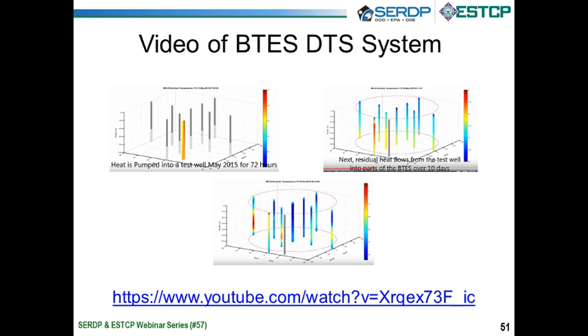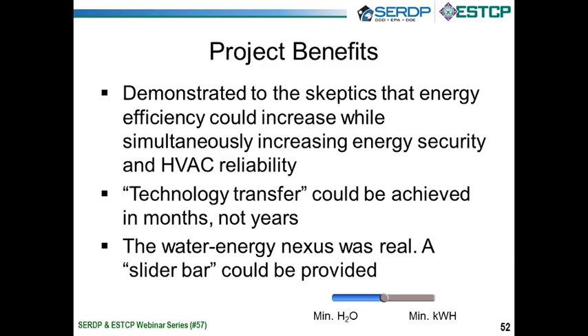The 3 slides there illustrate the heat we pumped down in the upper left corner during the thermal conductivity test. The second slide represents that heat flowing out into the bore field. And the last slide is an illustration of when the system is actually operating, the cold at the core of the bore field and then the heat at the perimeter. So feel free to look at that online later.